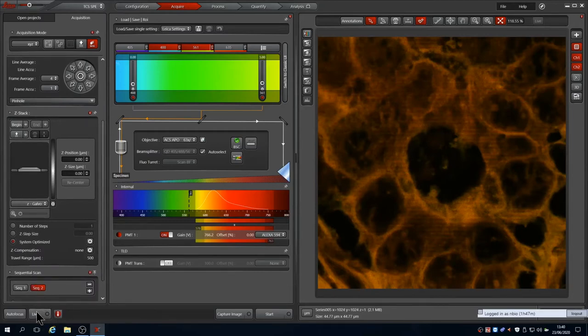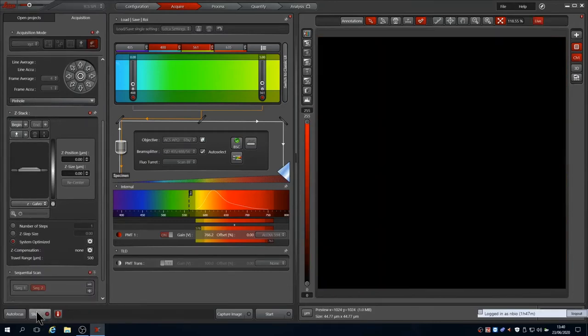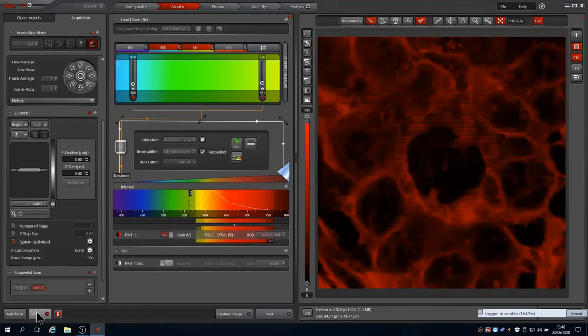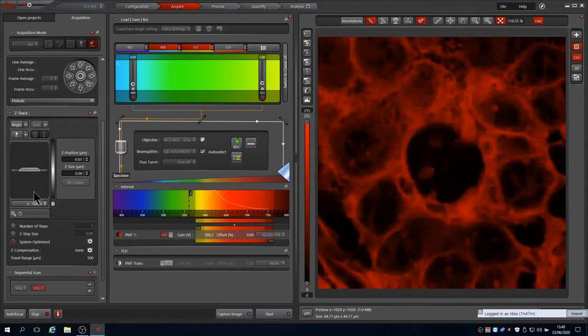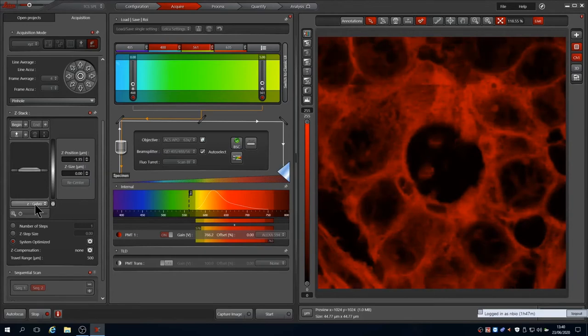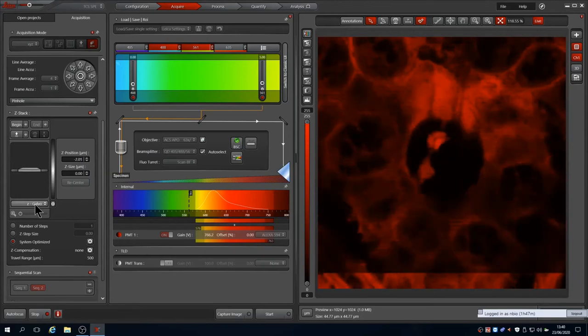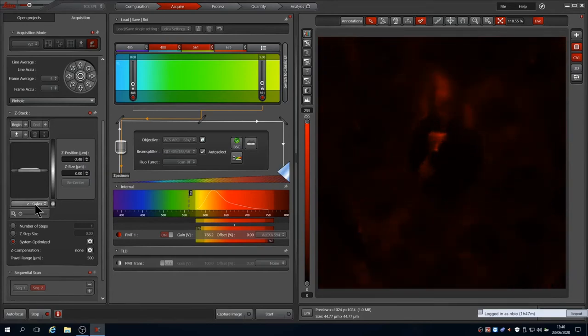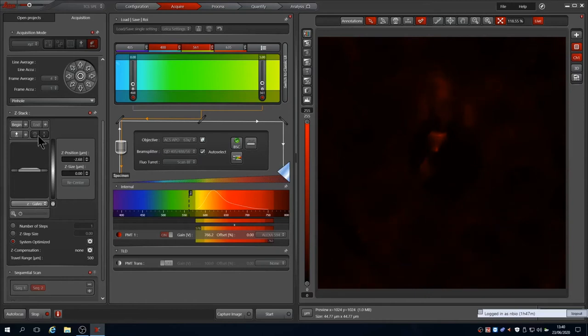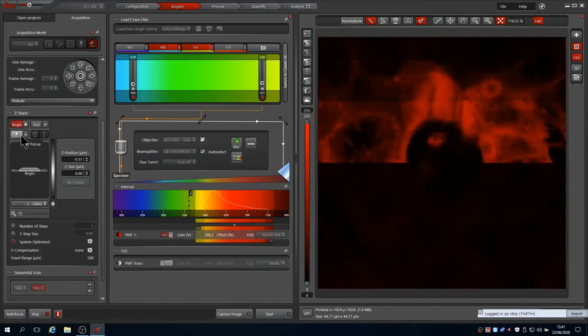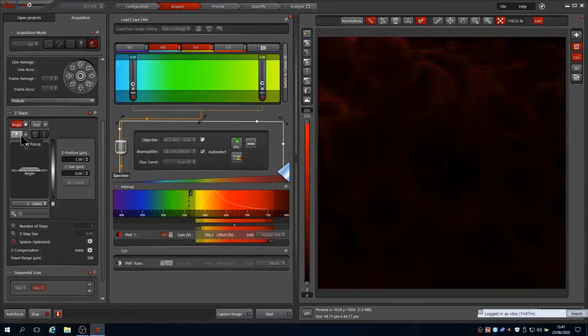It is important you do this with the Z-Stack that the Z-Stack will be taken with. By default this is the Z-Galvo drive. This is only controlled by the knob and the control panel under the monitor. Whilst live, adjust this anti-clockwise until just out of focus below your sample, then click begin. Now move back through the sample and out of the other side and click end.